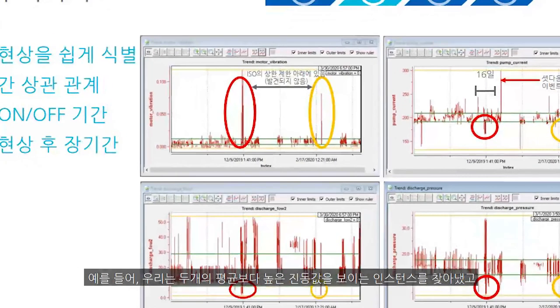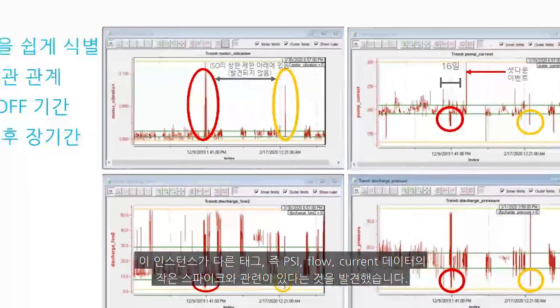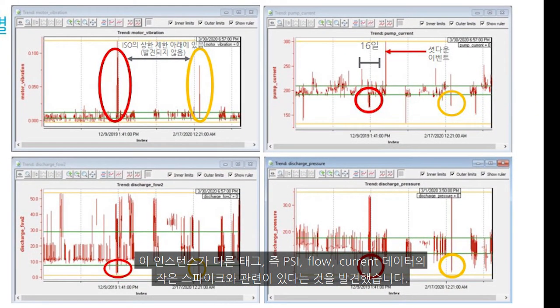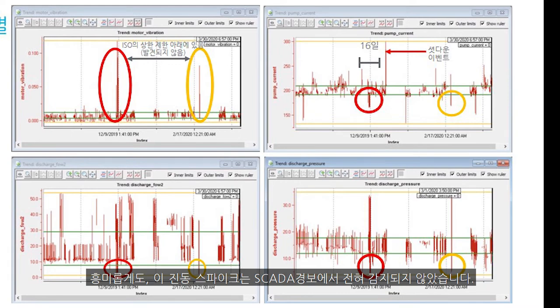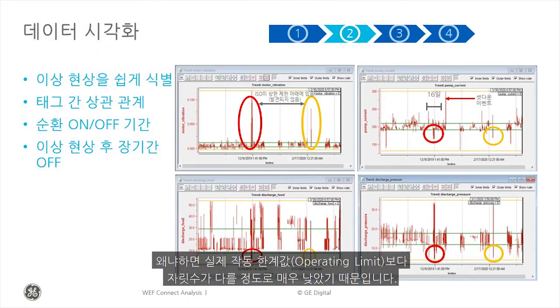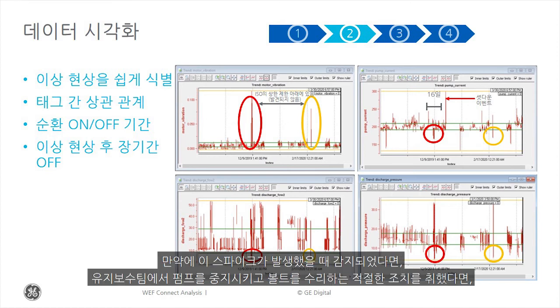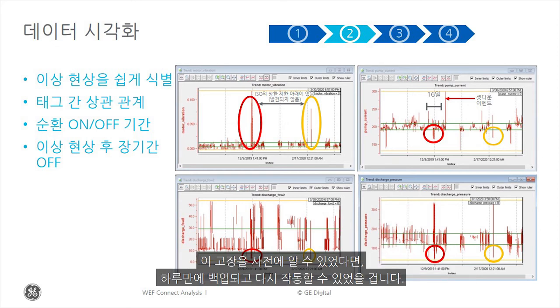For example, we found two instances of higher than average vibration that appeared to correlate with smaller spikes of data with other tags, such as PSI, flow, or current. Interestingly, this spike in vibration had gone completely undetected in the SCADA alarms because it's actually orders of magnitude below the operating limit. Now, if it were detected when it had occurred, and if the team had taken proper action to stop the pump and simply repair the bolt, had they known about it, they would have been back up and running within a day.